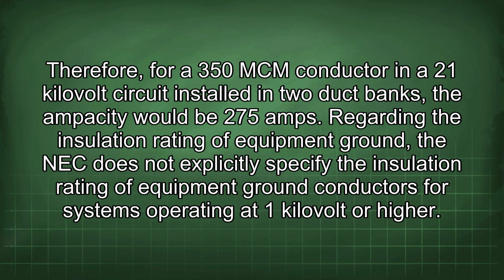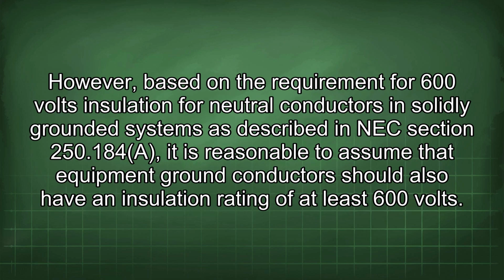Regarding the insulation rating of equipment ground, the NEC does not explicitly specify the insulation rating of equipment ground conductors for systems operating at 1 kV or higher. However, based on the requirement for 600 volts insulation for neutral conductors in solidly grounded systems as described in NEC section 250.184(A), it is reasonable to assume that equipment ground conductors should also have an insulation rating of at least 600 volts.